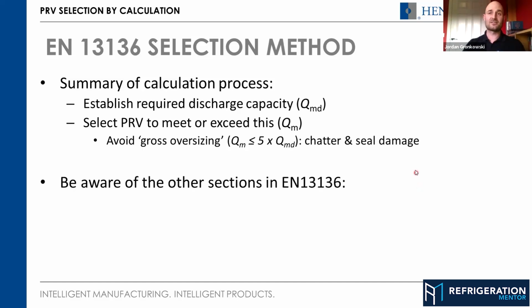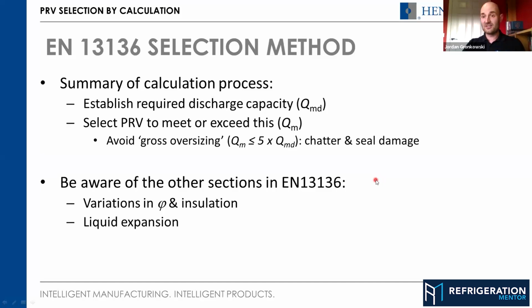A couple of other sections of the standard, just to make you aware that it's there. Variations in the phi term, which was the density of heat flow rate. Again, if you've got insulated vessels, that term can vary a little bit from the 10 that is stated as recommended in the standard. Liquid expansion is a little bit of a different beast compared to gas, because gas is compressible, liquid isn't, so it behaves slightly differently. You do need to make sure, if you're fitting a valve on a liquid line, that you use a valve that is rated for liquid discharge. Henry valves are all rated for gas discharge only, so they shouldn't be used in the liquid line. You do get special valves that are rated for liquid.